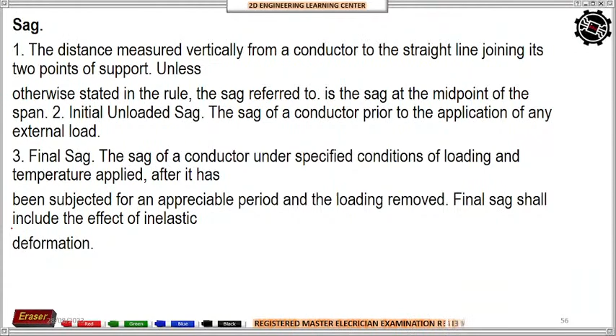Basically, ang sag pertains to or is caused sometimes by the weight of the wire or yung mga weight ng mga devices na i-attach natin sa distribution lines. May certain standard na dapat ito lang yung vertical distance ng sag - o yun, laylay. Sag is also to prevent your voltage to ground, yung tinatawag na measurement between the lines and the ground, para hindi magkaroon tayo ng grounded system o ng ground fault.